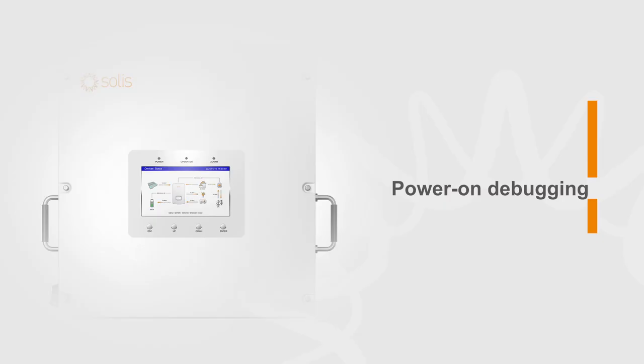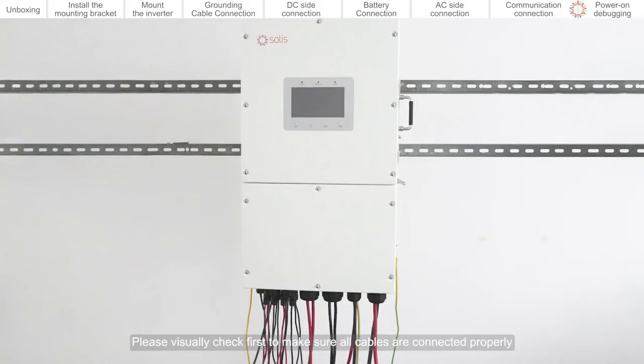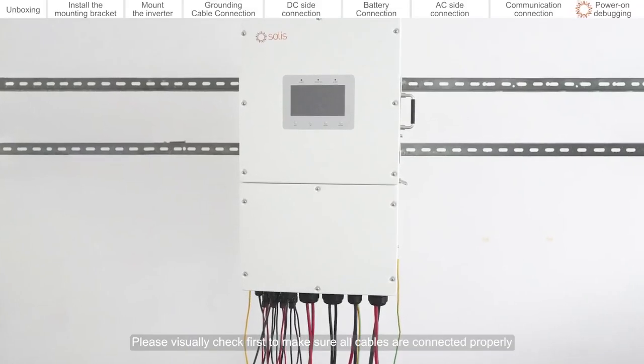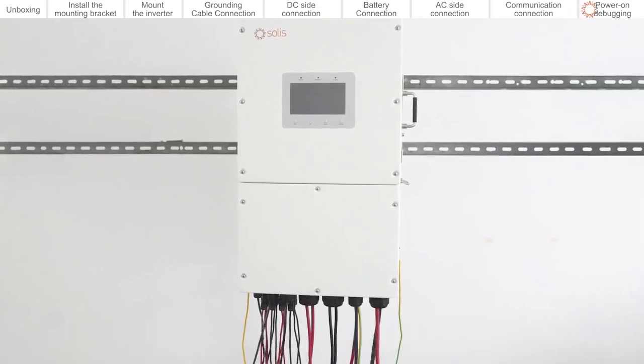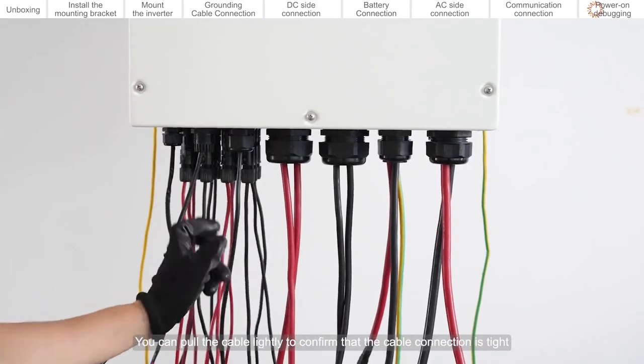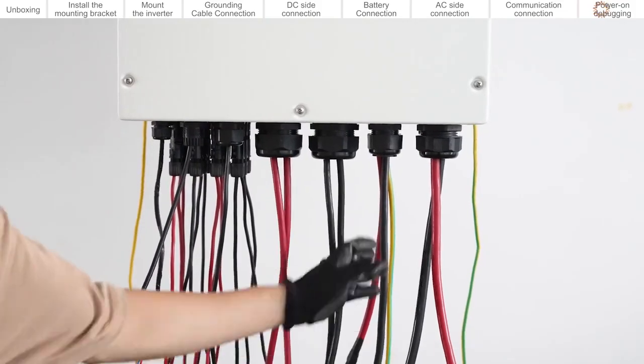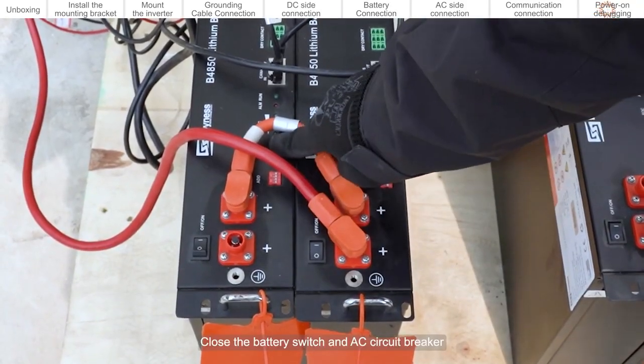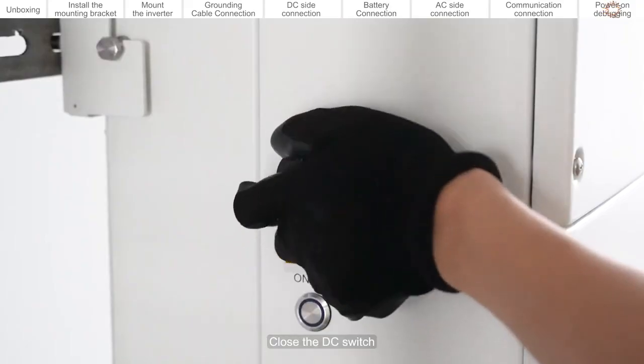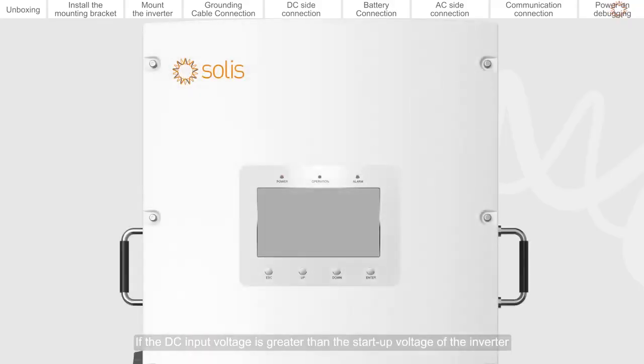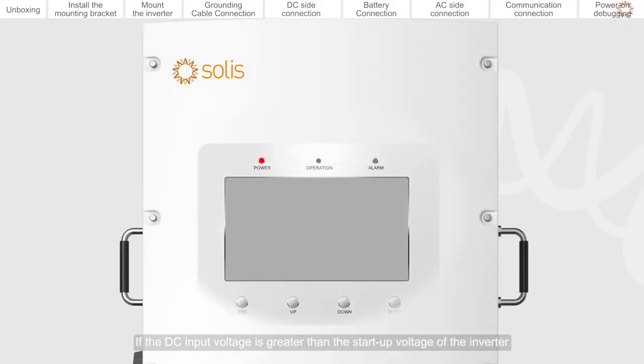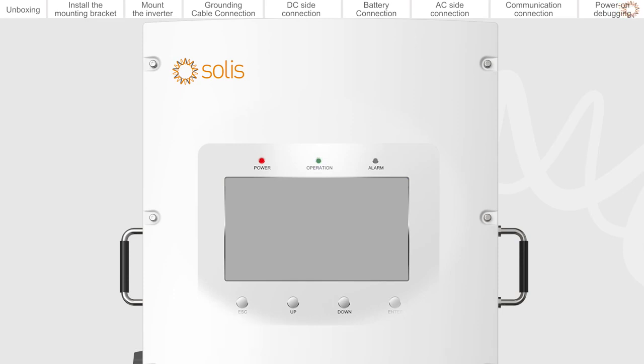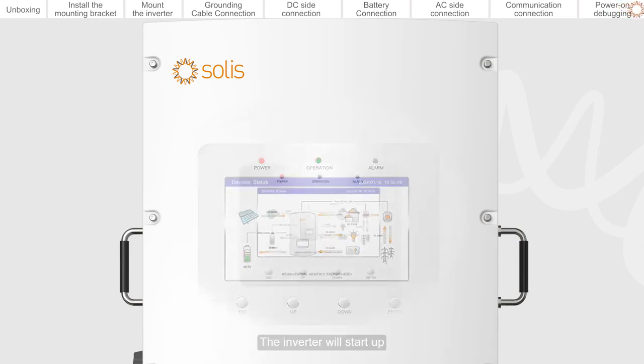Power on debugging. Please visually check first to make sure all cables are connected properly. You can pull the cable lightly to confirm that the cable connection is tight. Close the battery switch and AC circuit breaker. Close the DC switch. If the DC input voltage is greater than the startup voltage, the inverter will start up.